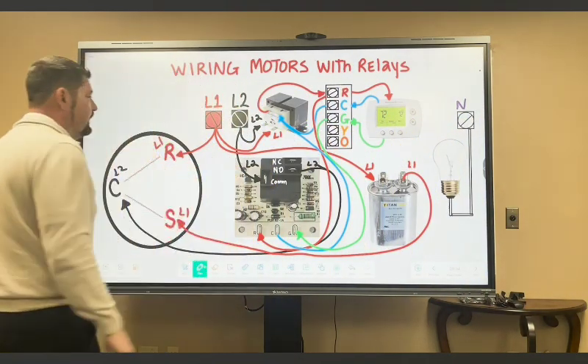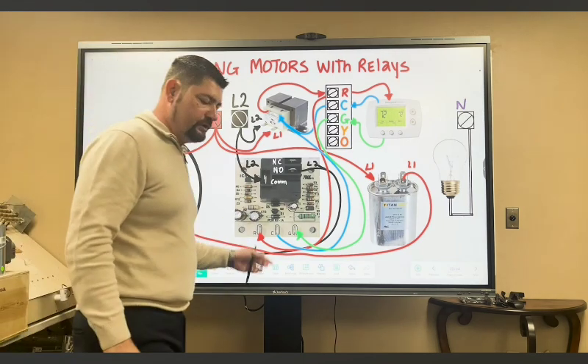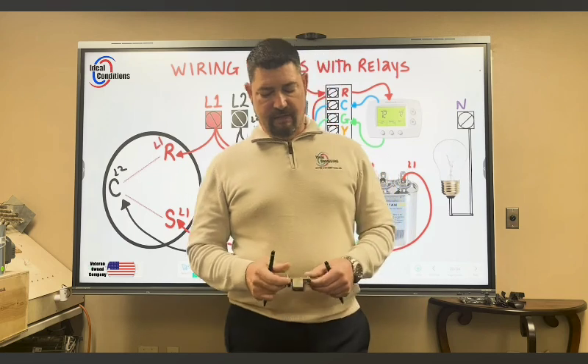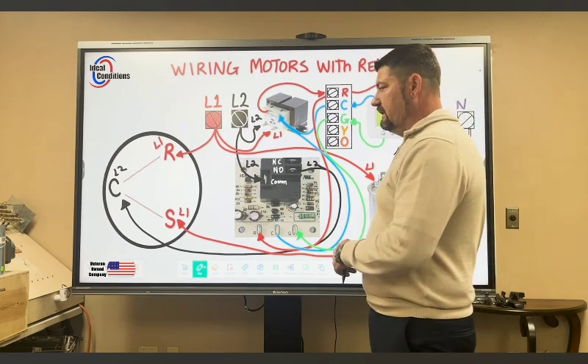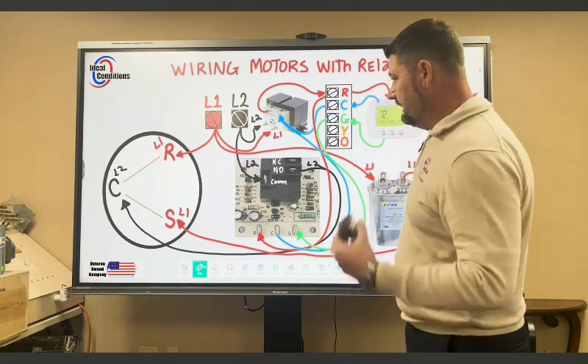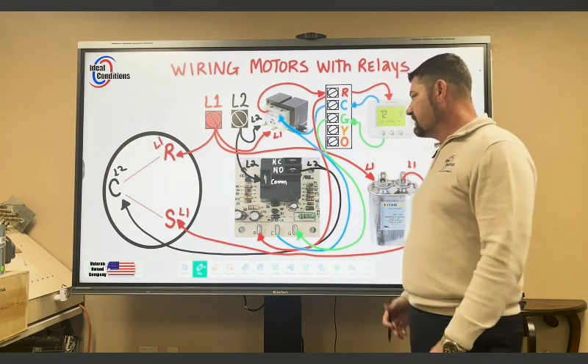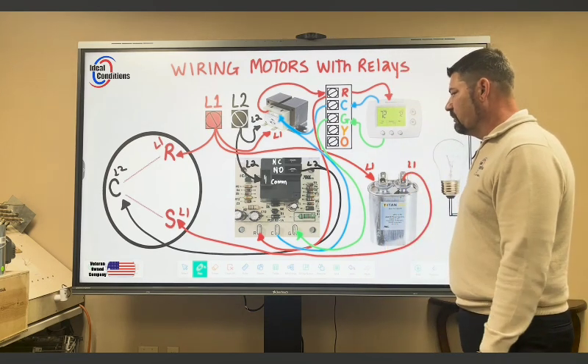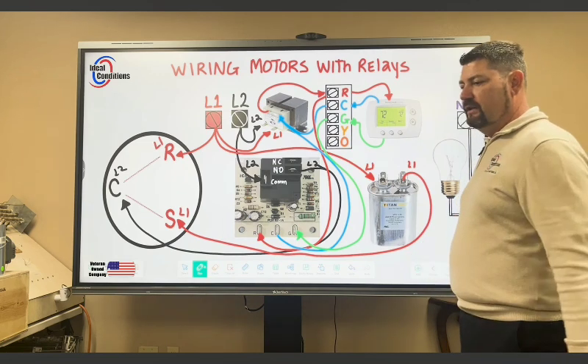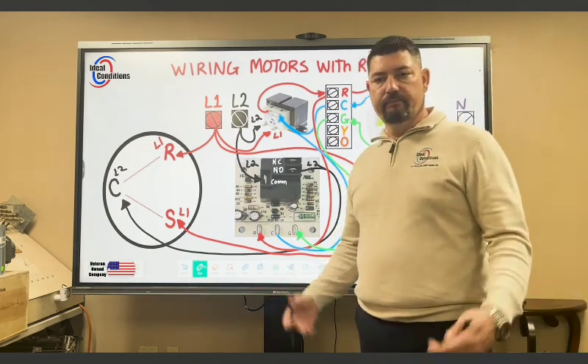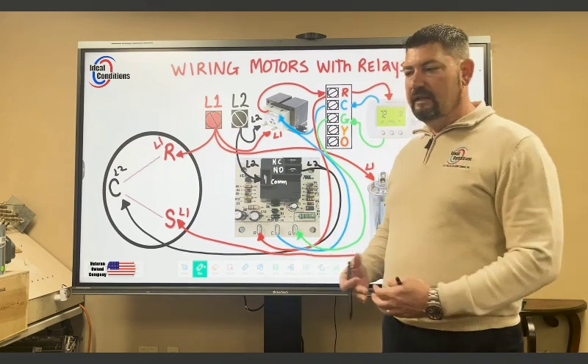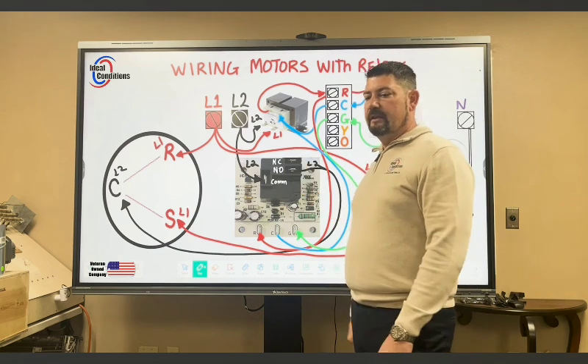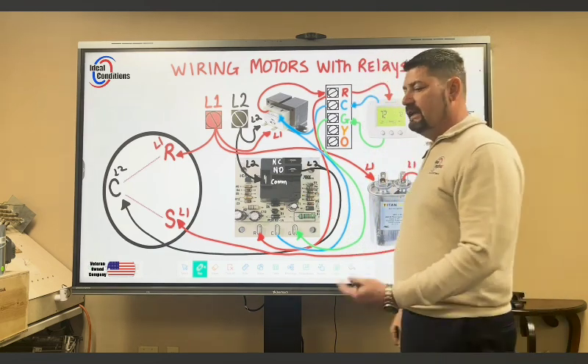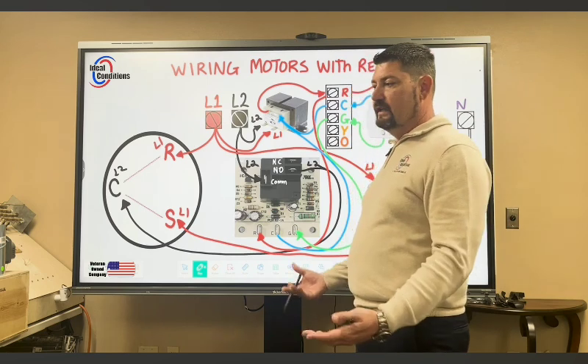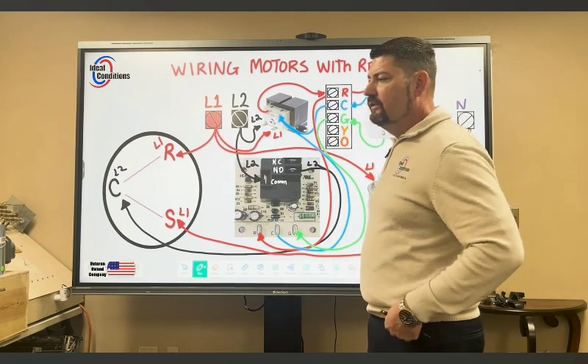The ICM255 blower control board is not an expensive truck stock item. If I wanted to carry one of these as a permanent fix, because I had to convert an ECM motor back to a PSC, I would probably put one of these in there as opposed to a relay, just because I'm getting more efficiency. I think the customer would like that too. Plus, relays make a pretty loud harmonic sound inside. The air handler is filled with metal. It has a clicking noise, and these are a very quiet choice. So you don't hear that click like a 9340, a 9380, or a contactor, or anything else of that choice would do.